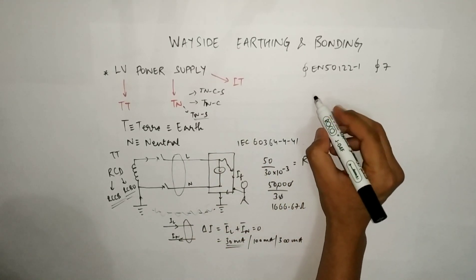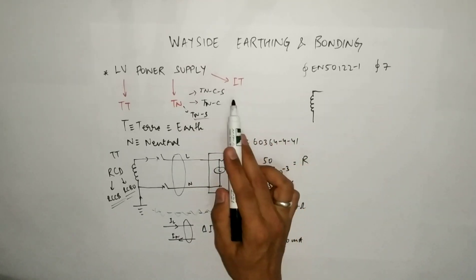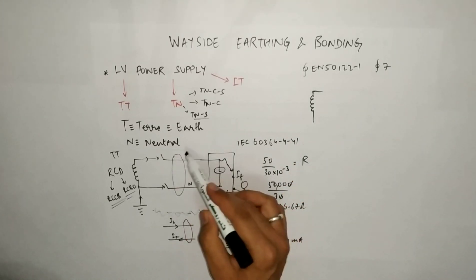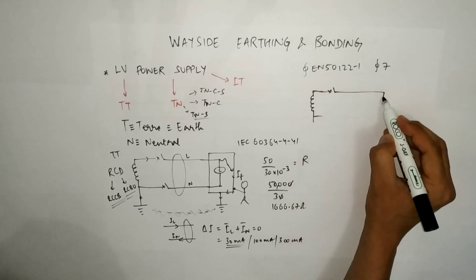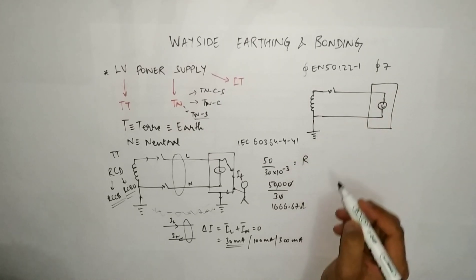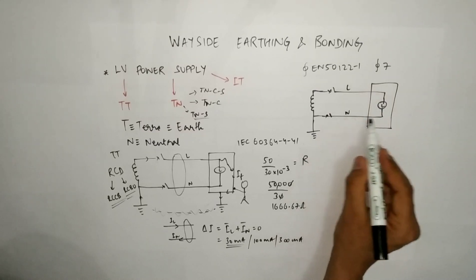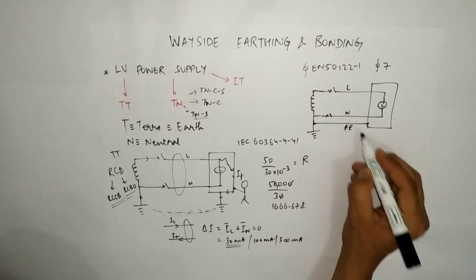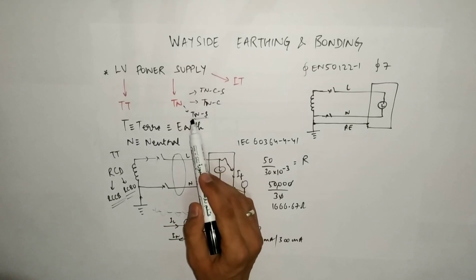In the case of TNS, you have a separate dedicated source. Even if MV or HV power is coming in, you convert it using a separate dedicated transformer at your source end, isolating both circuits. From this transformer you feed your load. The enclosure earth and the neutral will be separate. The neutral line is separate and the earthing for the enclosure is separate. From here you provide a dedicated conductor called the PE conductor — protective earth. Neutral and earth are separate for this equipment enclosure, which is why S in TNS represents 'separate' — earth and neutral are separate.